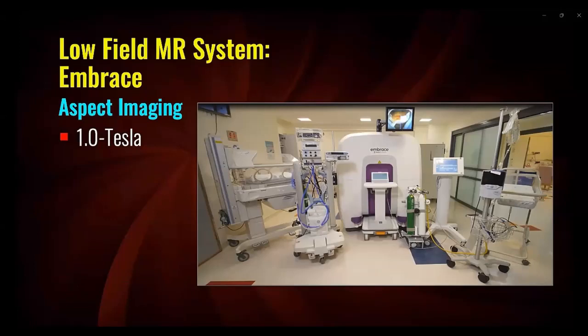Note the presence of a standard incubator, conventional physiological monitoring equipment, a ventilator, an infusion pump, and steel oxygen tanks, all positioned in close proximity to the neonatal MR system.